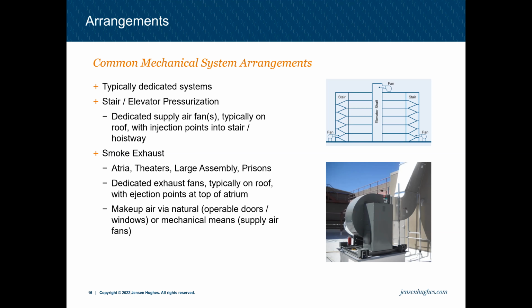Something that's important to recognize is that the larger fan does require ductwork space, and that's usually next to our stair enclosures. So it's just something to keep in mind in terms of floor plan and coordination, to make sure that we have the space for that ductwork. Smoke exhaust, like we mentioned before, is in atria, theaters, large assembly, and prisons.